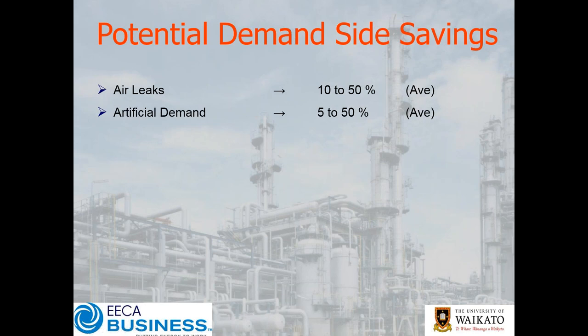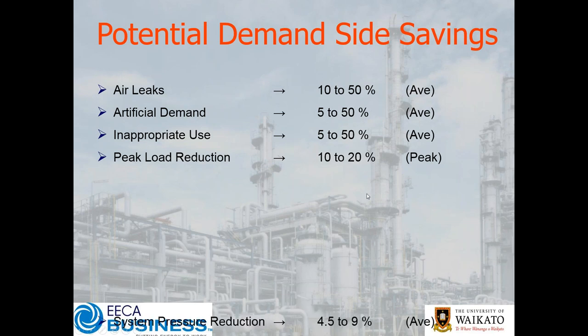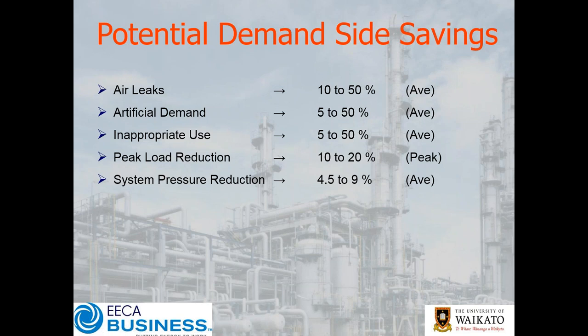Artificial demand — we'll define that shortly — once again five to around 50% savings quite readily achievable. The mix depends largely on the end use of air and the nature of the system. Inappropriate use — we'll differentiate between those two shortly. We have peak load reduction: can the peaks be managed other ways as opposed to just sizing a bigger compressor? And we have system pressure reduction, which we'll discuss towards the end. That four-and-a-half to nine percent is typically what you'll get in terms of the power consumption of the compressor.